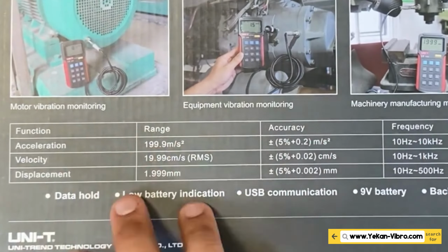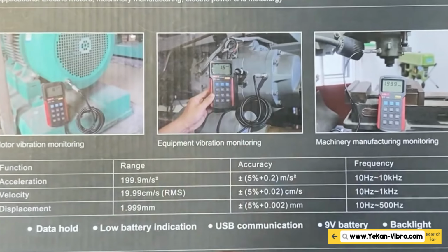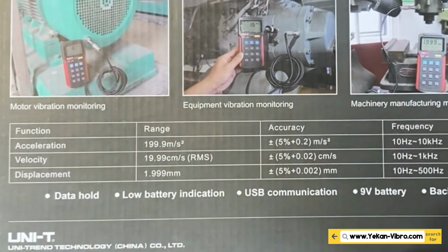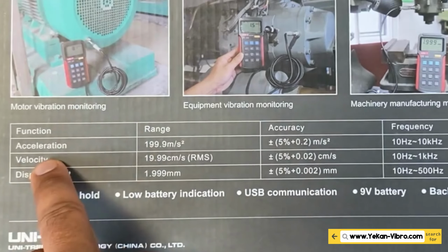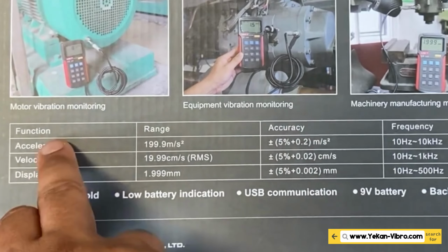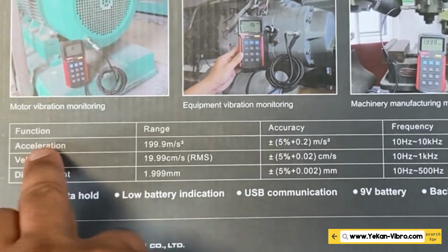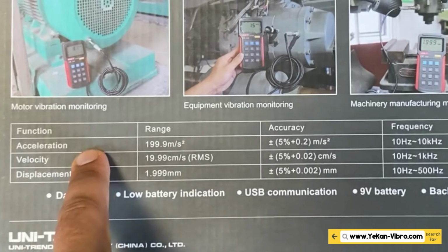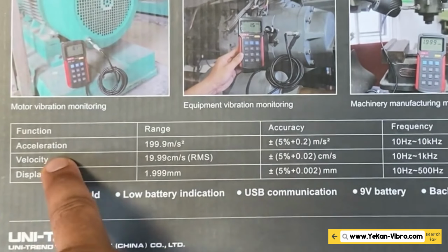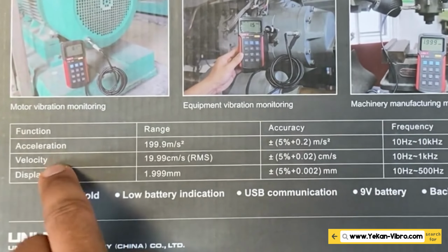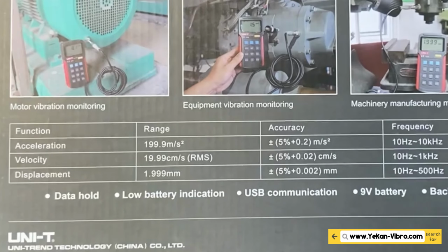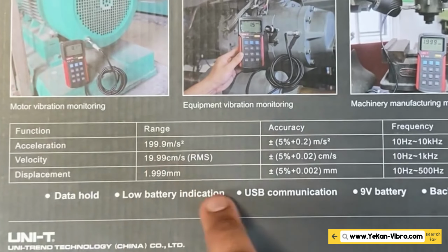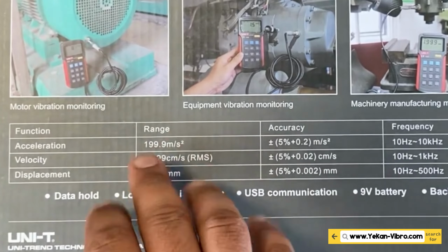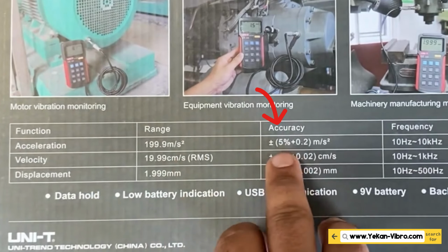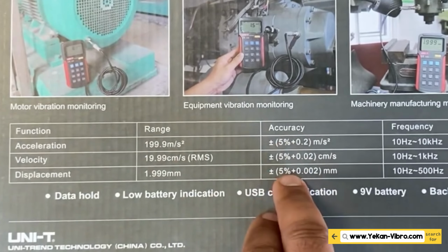Keep in mind the sensors connected to these, which are visible in their photos and also when we open the box to review. All of them are acceleration. So actually these do not have velocity and displacement. They come by integral calculation from acceleration, and by taking the integral over time, velocity is obtained, and from velocity by integral, displacement is obtained. These ranges that are written, the higher ranges definitely have error, but the lower ranges are more important. Accuracy of 5% is also a reasonable accuracy.